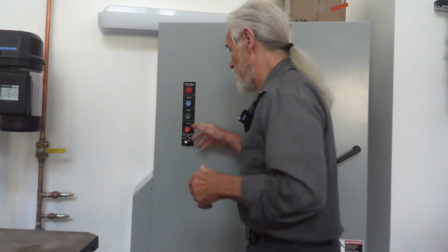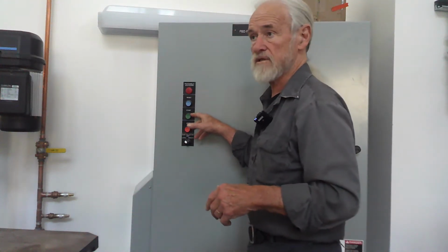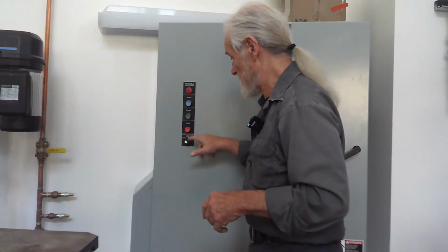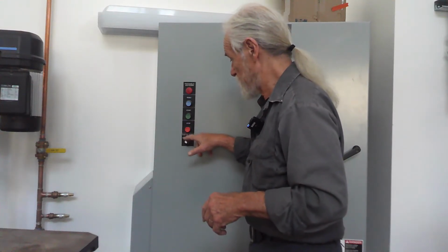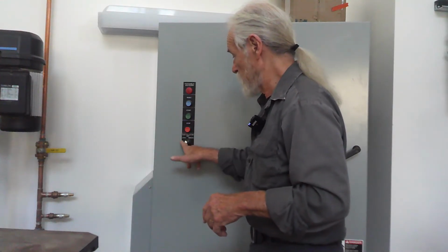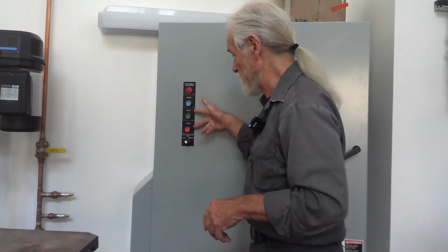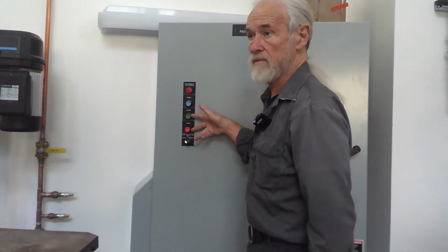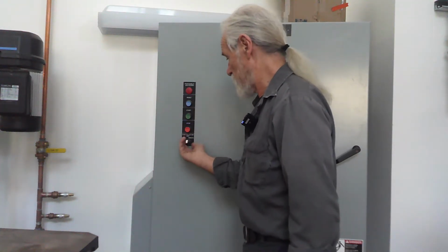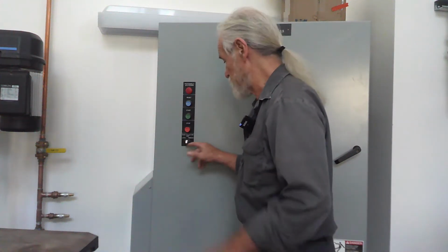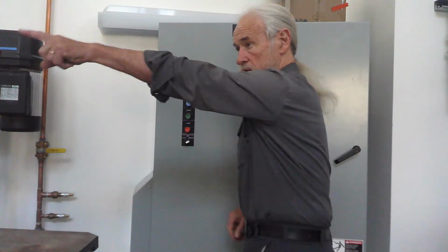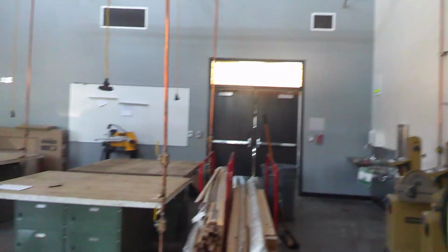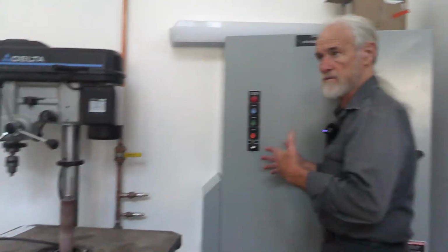Now there's two places to start and stop this thing. This is one, and that's what this refers to - this is the dust collector control. Local control is here: start and stop, like manual. Off means nothing happens. Remote means, by the door there, to the left, there's a red button we run - that's the same as this. It's a momentary switch, both of them.